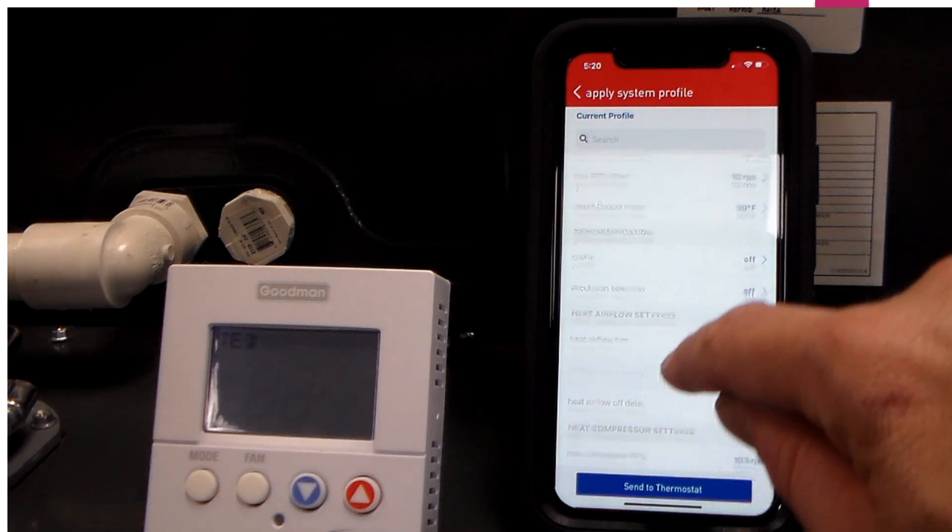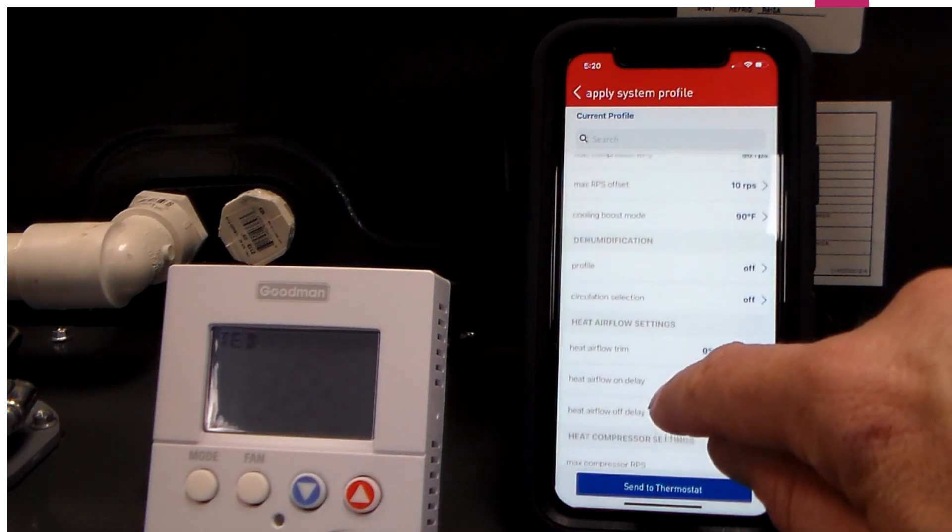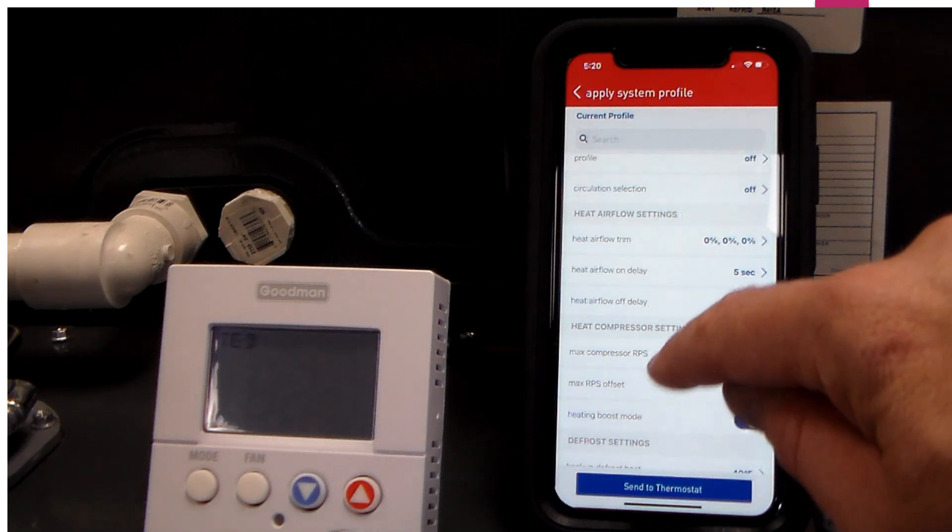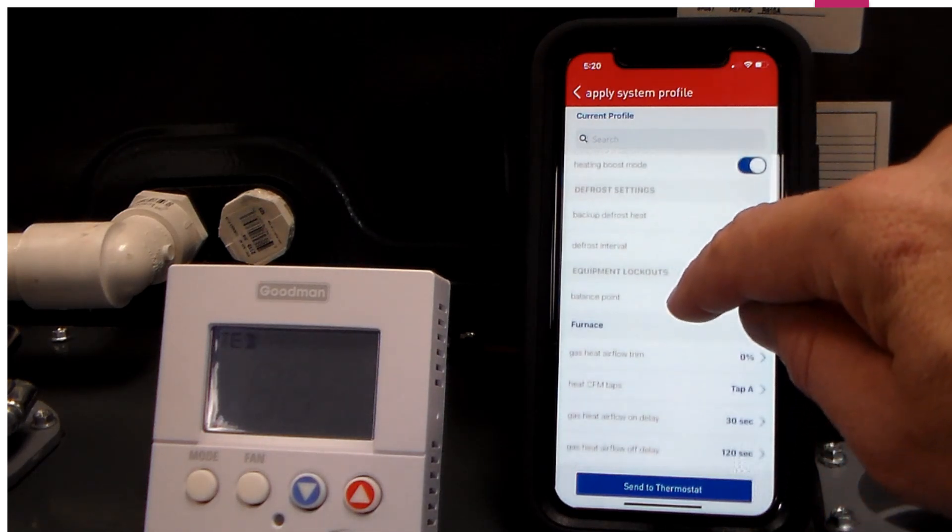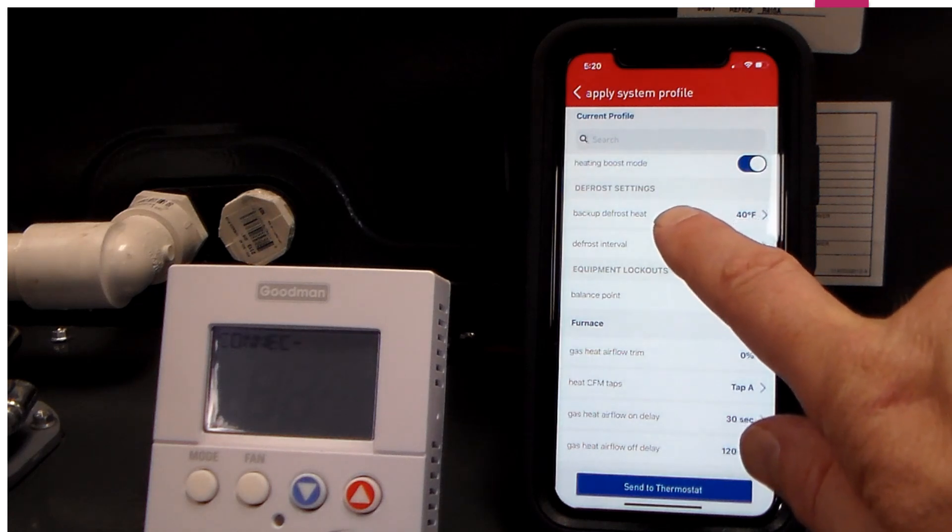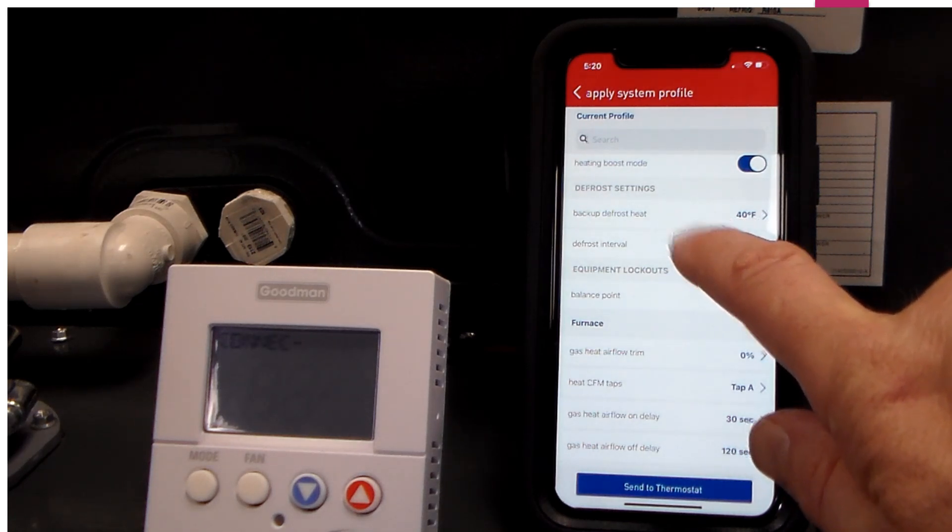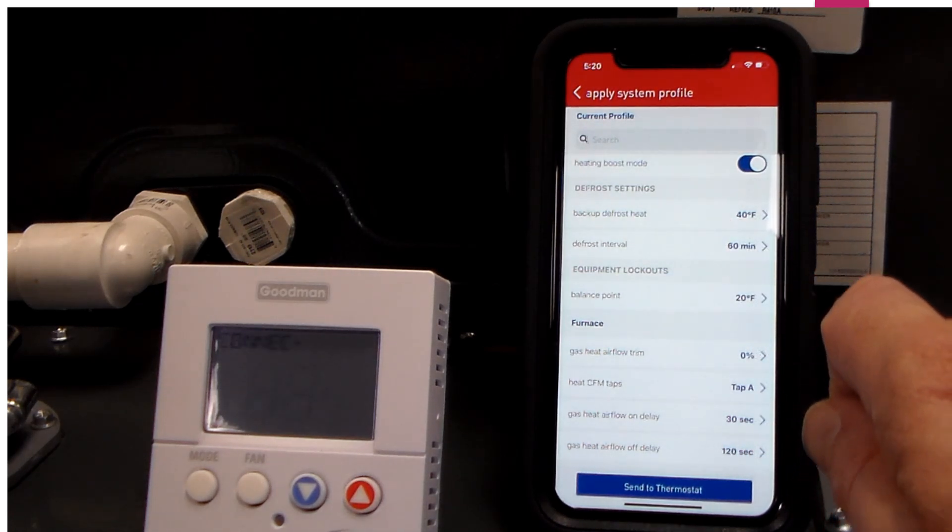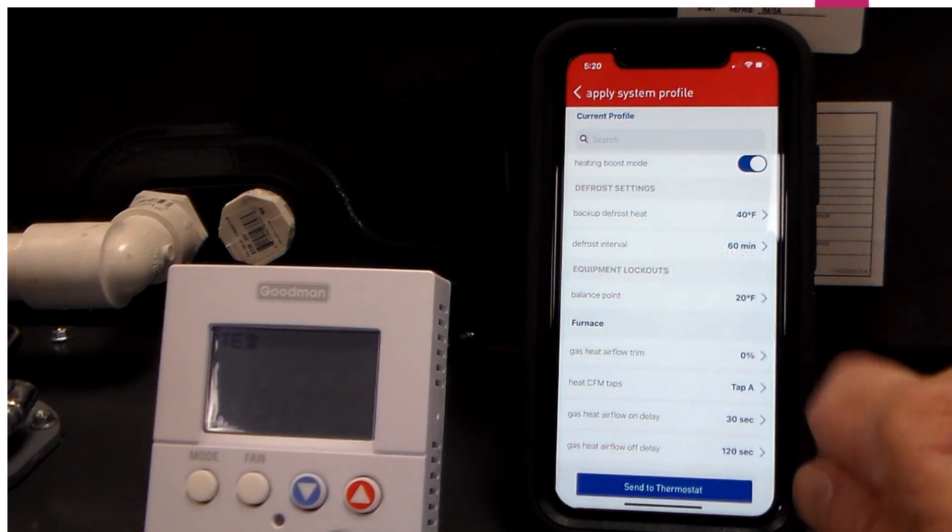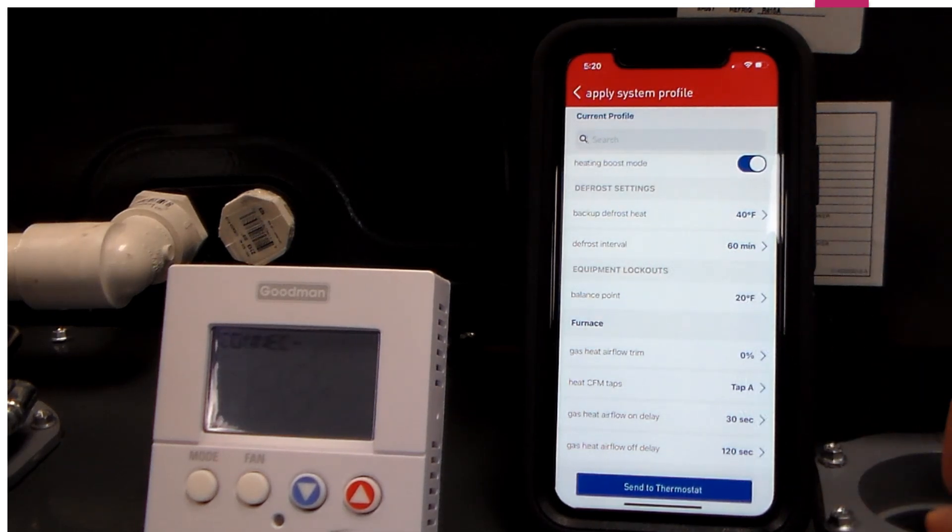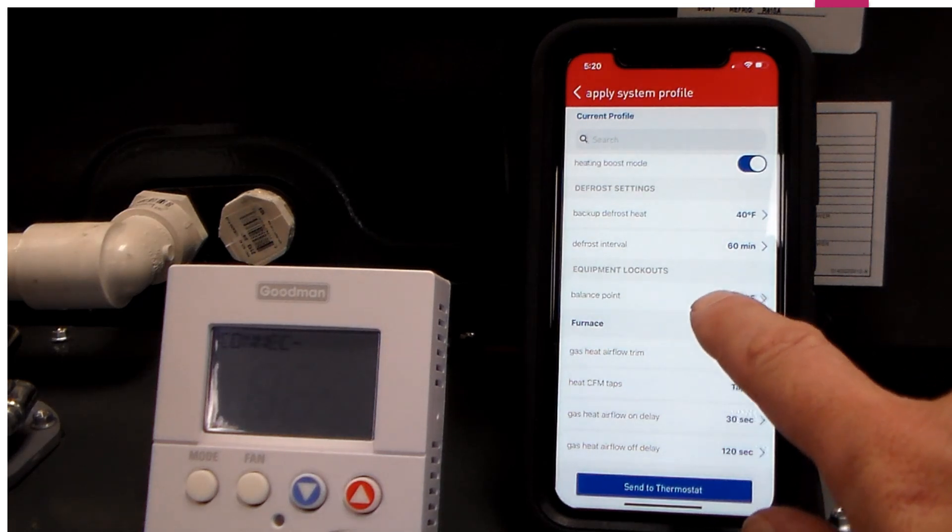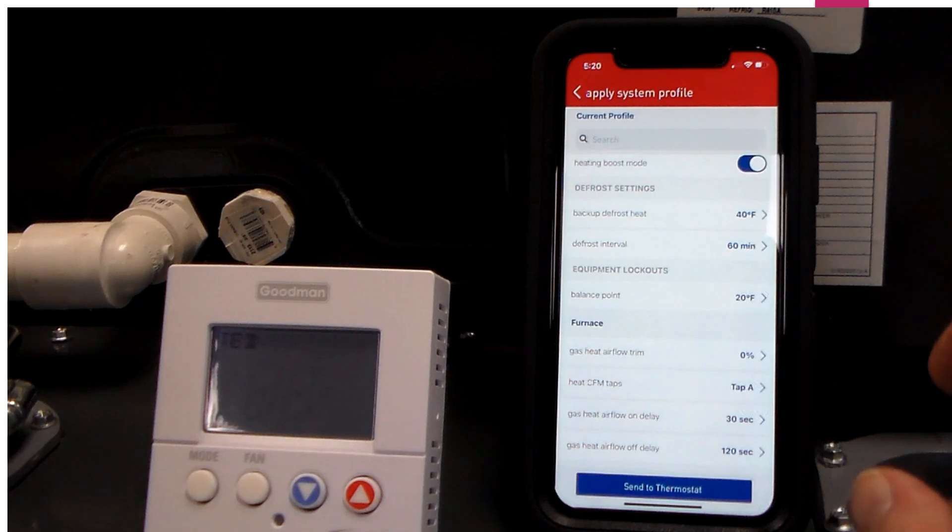We also have our heat airflow settings here where we can trim our airflow up and down if we like. We have our backup defrost heat temperature that we want to engage our backup defrost heat on. We also have a defrost interval that we can set for whatever time in between defrost cycles we want to start with. And on a dual fuel system, we have a balance point that we want to set.